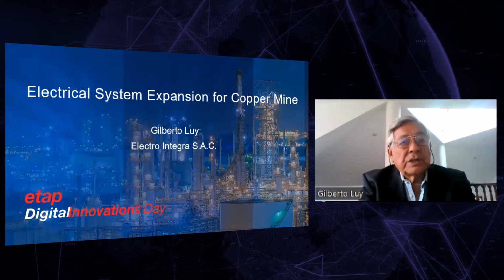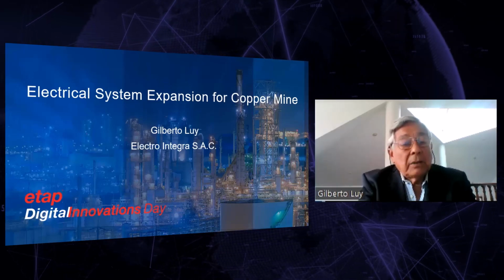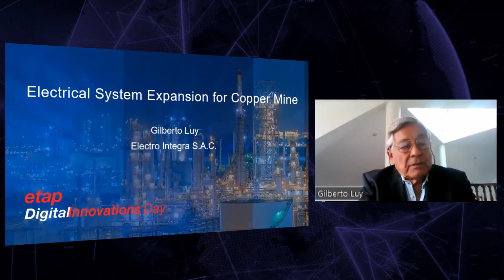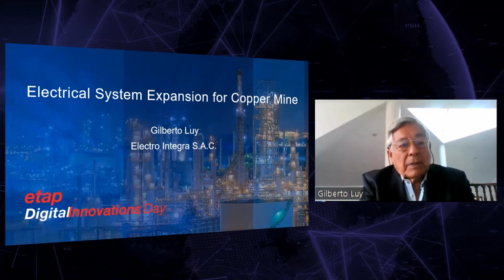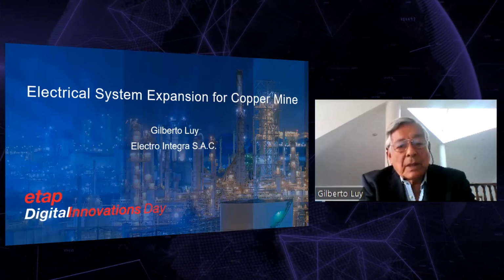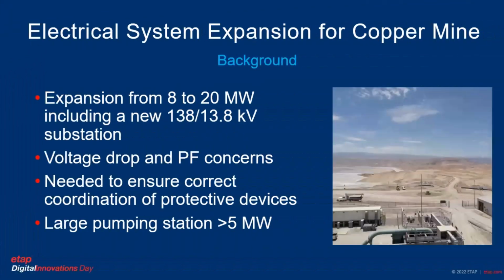So the electrical system has to be reliable and efficient in order to have a process which is continuous as much as possible. As background, the present power consumption in the tailings dam is 8 megawatts, and the client required for the future up to 20 megawatts. And that included a new 30 MVA transformer.